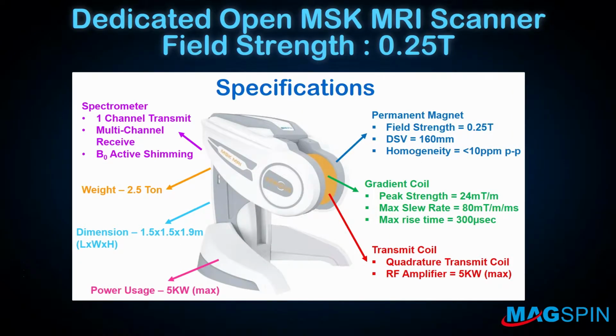The specification of this magnet is really low - it's 0.25 Tesla. We have a DSV of 160, and we manage to shim it down to less than 10 ppm peak to peak. We have a pretty good gradient coil at 24 millitesla per meter, with a rise time of about 300 microseconds. For the transmit coils, we use a quadrature transmitter with just 5 kilowatts of RF. The whole thing weighs about 2.5 tons. The dimensions of the magnet are 1.5 in length, 1.5 in width, and 1.8 in height. The total maximum usage is about 5 kilowatts for the most intensive sequences.